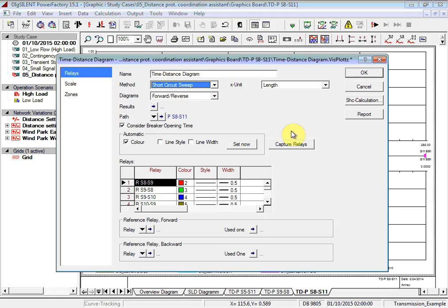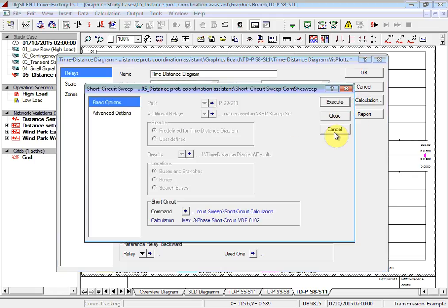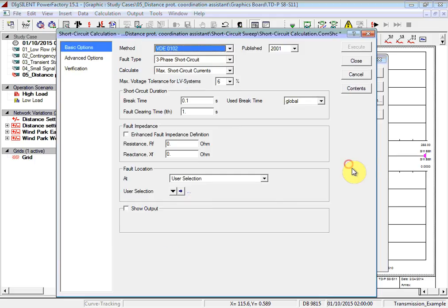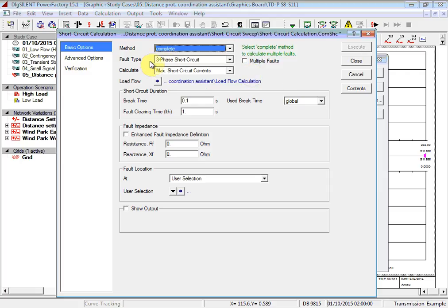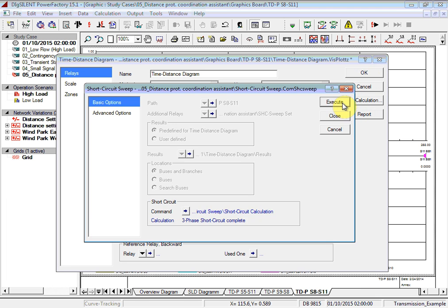With the short circuit sweep method selected, a new calculation will be carried out in the time distance diagram where short circuits will be applied at intervals along the length of the path and the actual tripping time of the relays will be calculated. Let's carry out the short circuit calculations. Press this button, Short Circuit Calculation. We're going to carry out a short circuit calculation in accordance with the complete method. We're going to carry out a three-phase short circuit at each location in the path, and we're going to calculate maximum short circuit currents.